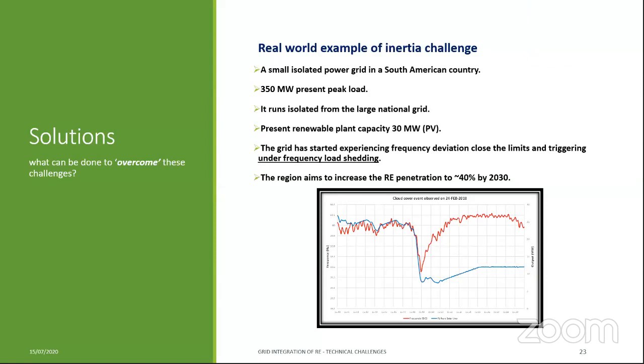So there was a cloud passage and the output power dipped from around 30 to around 15 megawatts, so nearly a 50% drop in the output power. That created a frequency drop almost up to 59.5 hertz, which is approaching the under frequency load shedding.